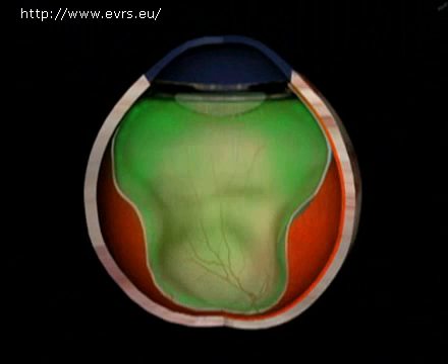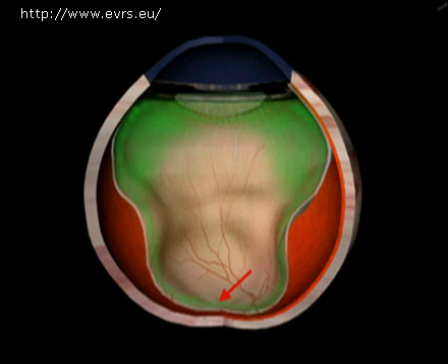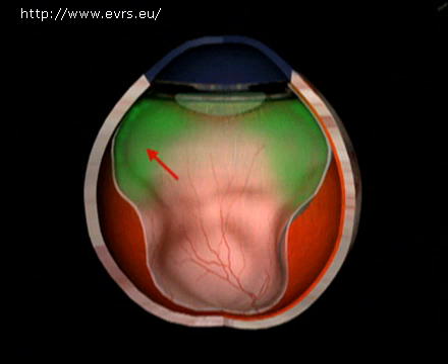Let's see now the aspiration flow. During a vitrectomy, it is necessary not only to remove the central vitreous, but also the posterior hyaloid, the anterior hyaloid, and the peripheral vitreous, all of which necessitate different aspiration flows.